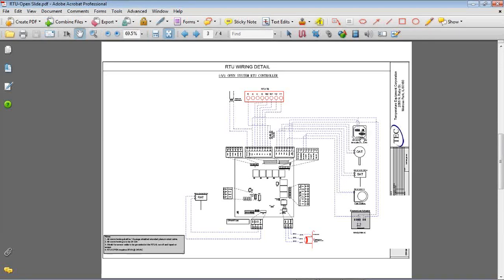So you see we have an enthalpy switch for outdoor air lockout. We have an outdoor air temperature sensor. We have a supply temperature sensor. And then we have a current transducer for fan status, and we actually wired to the economizer actuator here. So just kind of a general layout. We can provide these for you if required. Most of this stuff will be factory wired if you get the factory installed option. So this would only be for a field installed option, but something that we just do standard whenever requested as a policy here at TEC.